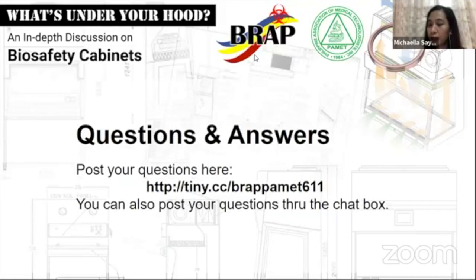So we have a question here. How would we know if the airflow is functioning well? That's one of the things that Mr. Louis said. You need to get your biosafety cabinet calibrated and certified. That's the only way to ensure that there's enough airflow going inside your biosafety cabinet and there is enough exhausted air being ejected. So you don't just look at the air that's going inside your biosafety cabinet, but also the air that's being exhausted, to determine if your biosafety cabinet is safe.